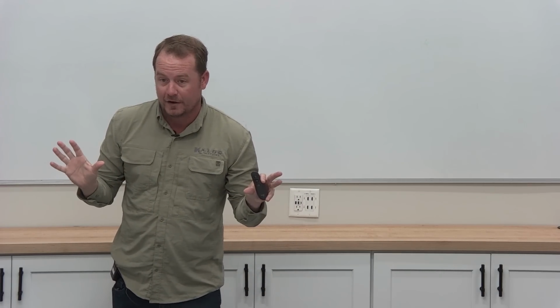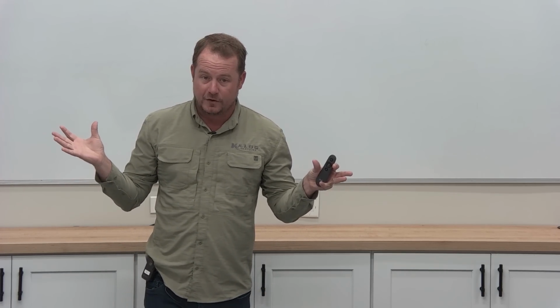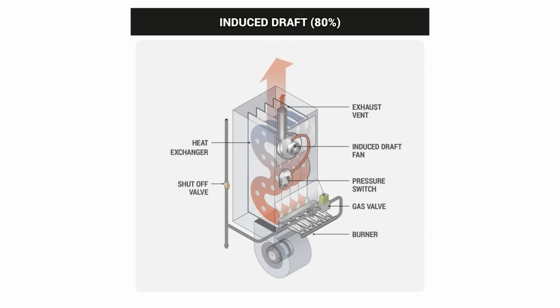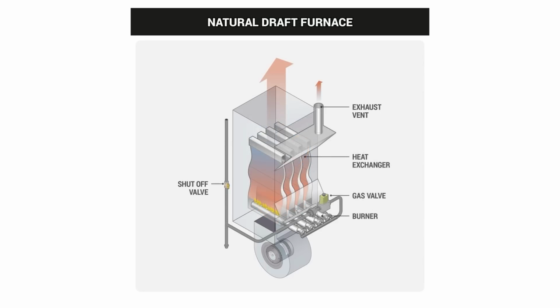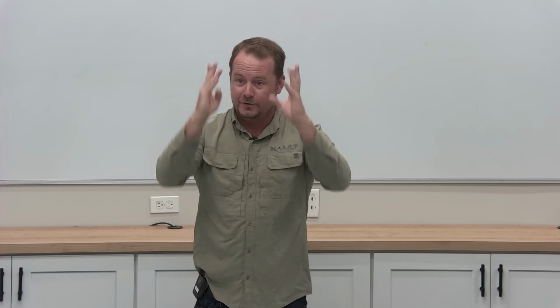And all that inducer fan is doing, that's why they don't call it a power venter. There is such a thing as a power vented furnace, but these aren't power vented. These are just induced draft. You're just inducing air, and the only reason you have to have induced draft is because our heat exchangers are complicated nowadays. Back in the day, if you go to an old natural draft furnace, go in there, you'll just see these flames that are just upright. They don't have these gun burners that shoot out at you. The flames just kind of do this, right? Like looking at a grill or something.